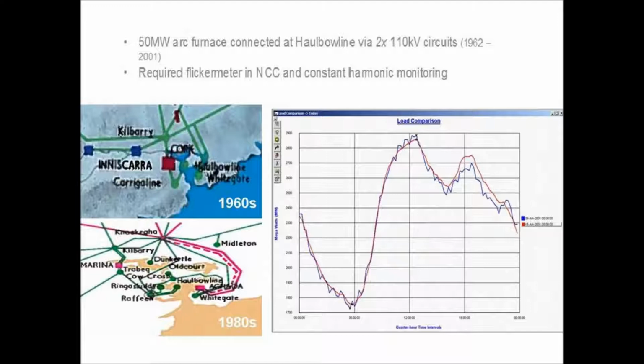So this is basically an SLD of Irish Steel and how they were connected. You can see that there are two SVCs connected into Irish Steel, and they were connected in an always-on configuration. If either of the SVCs were turned off, the harmonics became above the limits, the IEC limits, and Irish Steel had to go offline. So we had second and third order harmonics and a high-pass filter as well. That's just to give you an idea of what they were trying to filter out down there.